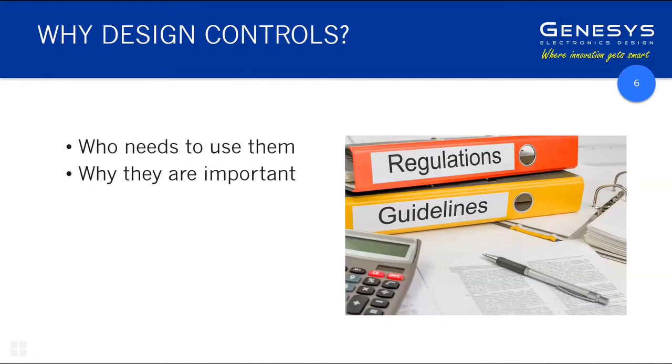So in terms of who needs to use them, the party that's responsible for them is the medical device manufacturer that puts the product on the market. They are not necessarily the entity that does the actual design and development work. So anyone who's involved in the design and development and also the product definition and specification needs to use design controls throughout the steps in the development process, which takes us nicely to the next slide.